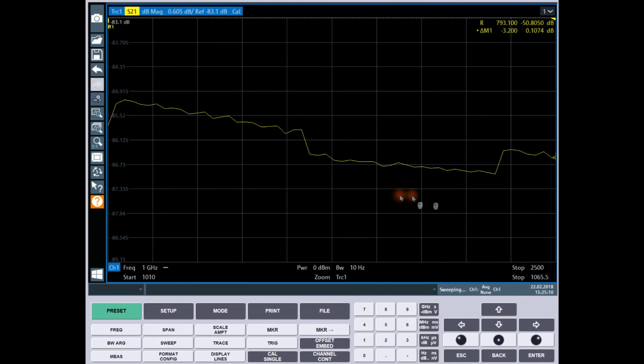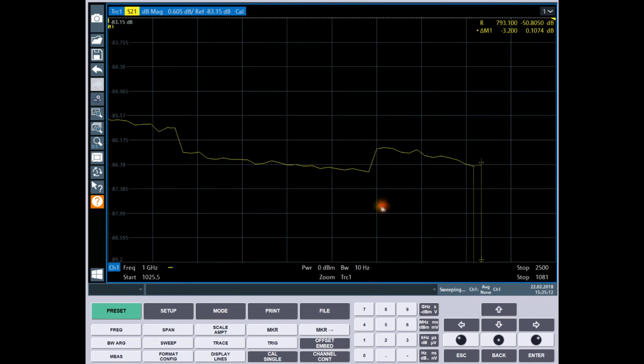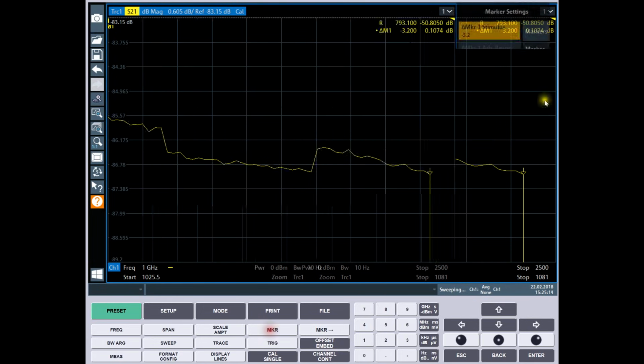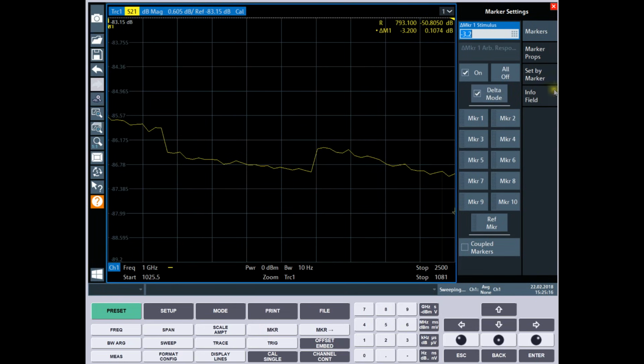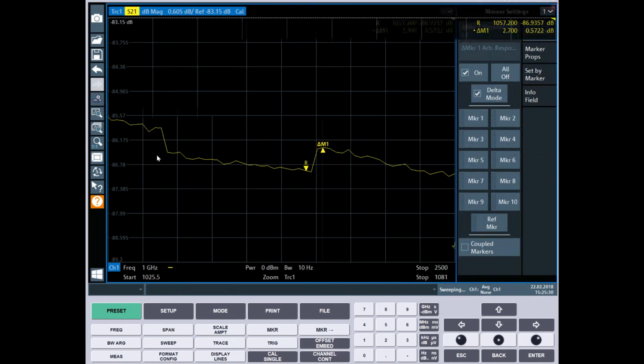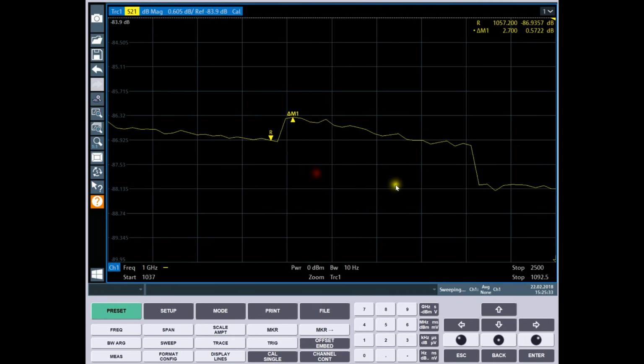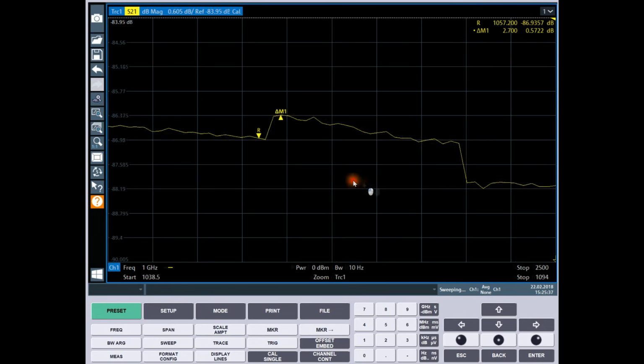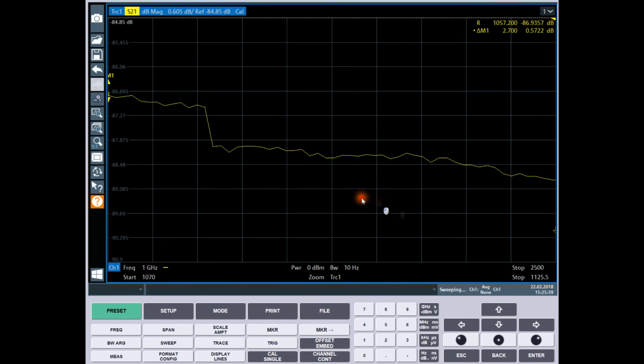So let's go ahead and look at some of these. Let's say this jump here, which we know what it's supposed to be. Let's grab the marker. I wish there was an easy way to bring the marker forward without having to create it again. So let's put the marker here, put the delta marker there, 0.57. So we are still catching tiny changes in loss at an attenuation of 86.9 dB. So this huge dynamic range and the repeatability of the instrument is what is being tested here, and we have no problem catching that. So I'm quite happy with that.